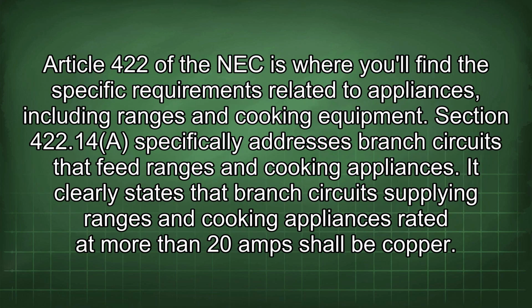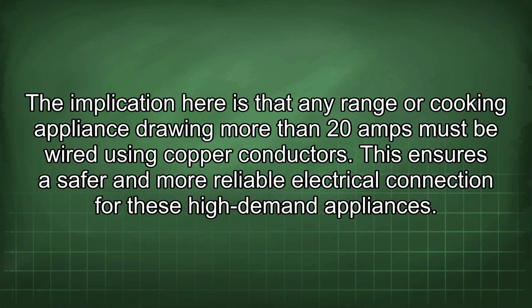Article 422 of the NEC is where you'll find the specific requirements related to appliances, including ranges and cooking equipment. Section 422.14 specifically addresses branch circuits that feed ranges and cooking appliances. It clearly states that branch circuits supplying ranges and cooking appliances rated at more than 20 amps shall be copper. The implication here is that any range or cooking appliance drawing more than 20 amps must be wired using copper conductors. This ensures a safer and more reliable electrical connection for these high-demand appliances.